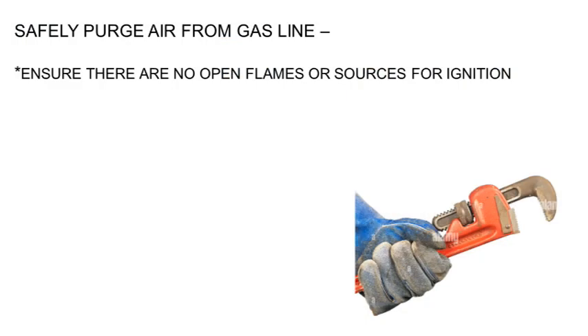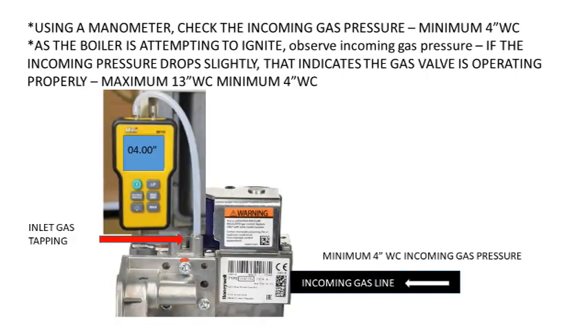Beyond looking at maintenance, follow the manual and check these items to uncover the cause of ignition failure. Is the gas line purged of air? Is there sufficient gas pressure? Using a manometer, check the incoming gas pressure — minimum 4-inch water column. As the boiler is attempting to ignite, observe incoming gas pressure. If the incoming pressure drops slightly, that indicates the gas valve is operating properly.